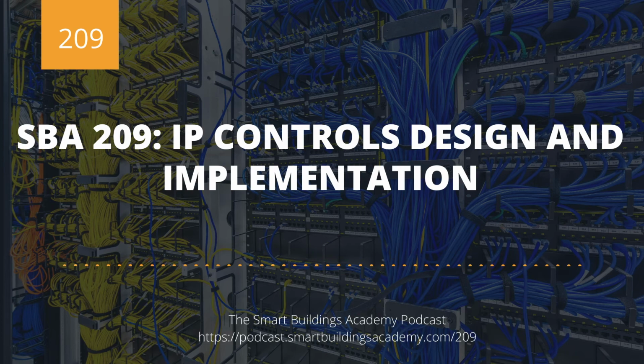Some folks will push back and say it's very difficult to get IP addressing approved on submittal sets. I would agree with you. IT usually does not have their IP addressing scheme worked out when you're going in the CD phase and you're working on your submittal set. That being said, you can still put address ranges. You can say, okay, we're going to use 192.168.0.1/24. And even if you end up using a 10 dot whatever IP address subnet later, because that's what IT wants you to do, that's fine. You at least have something to base your initial design and layout on.